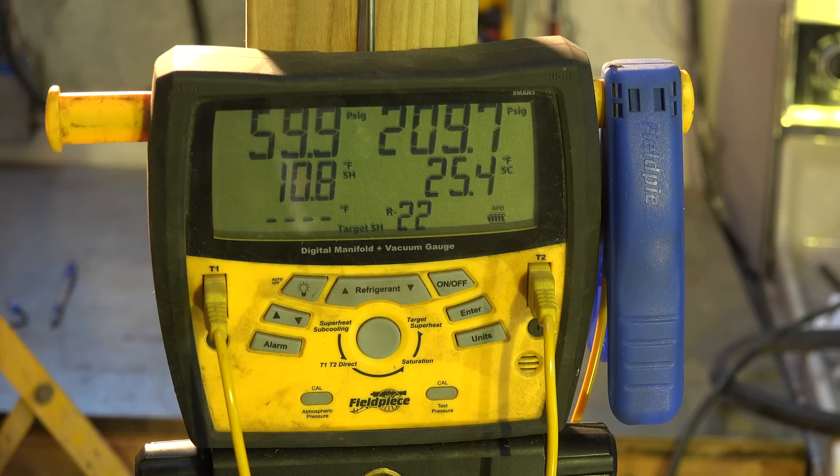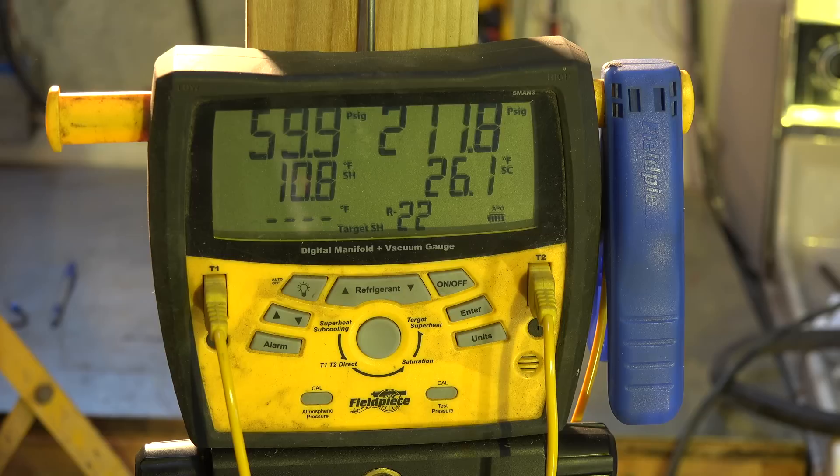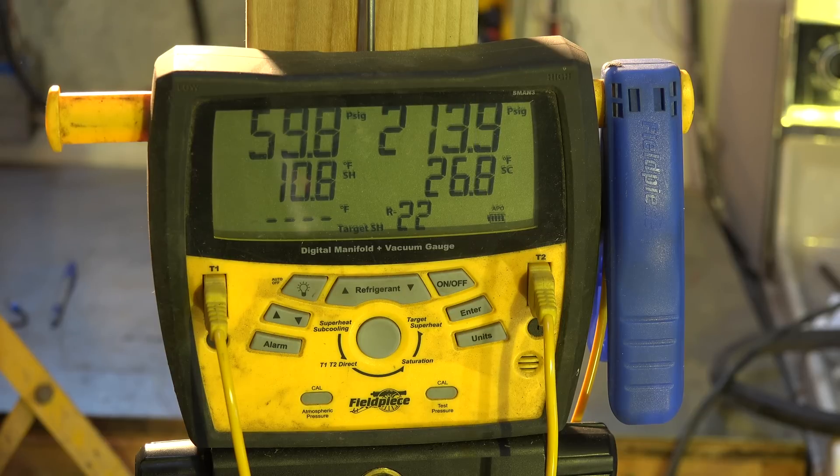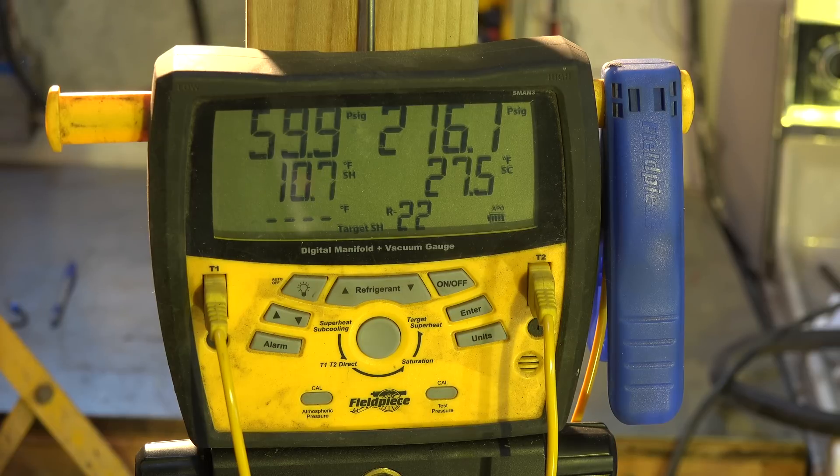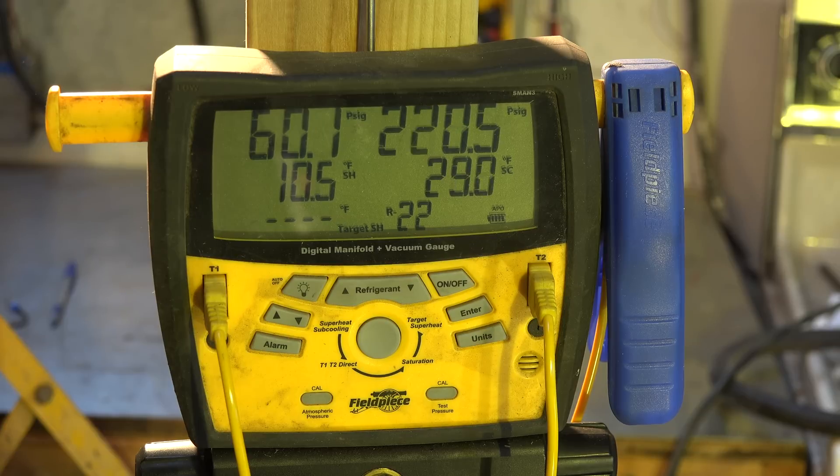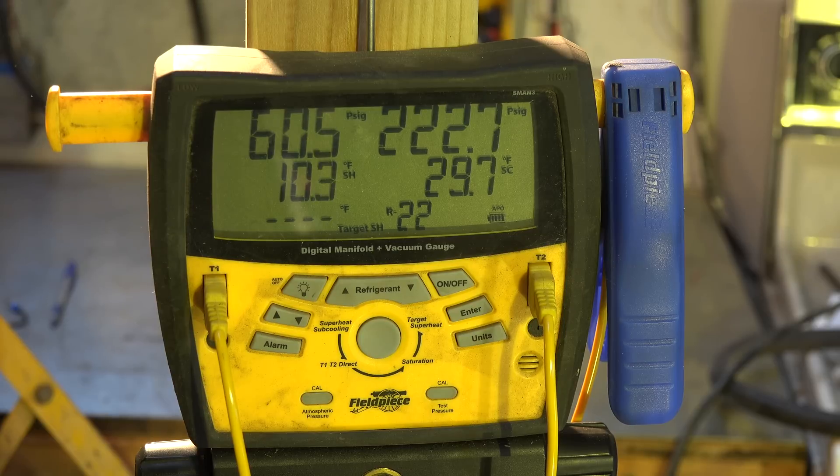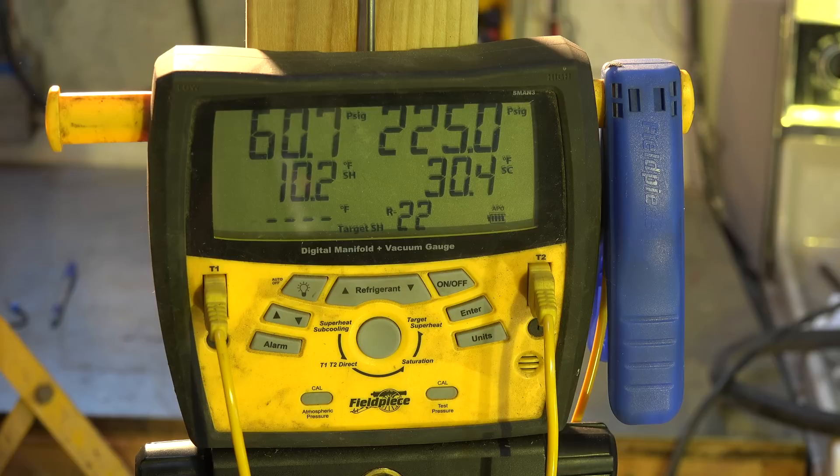Now we're running this at about a quarter speed so it's going to be pretty slow. Head pressure is going up. That of course is also going to increase the suction pressure. We're still about 10.5. Now the head pressure is going up so it's going to start dropping that superheat.